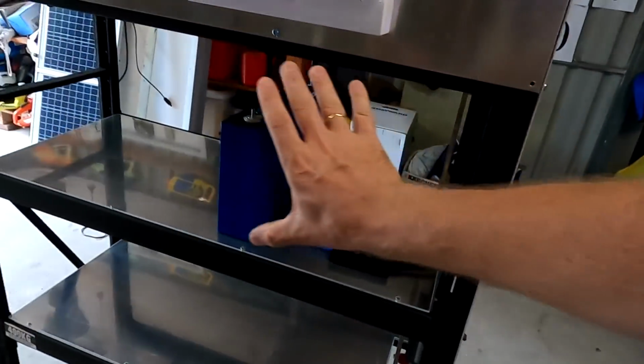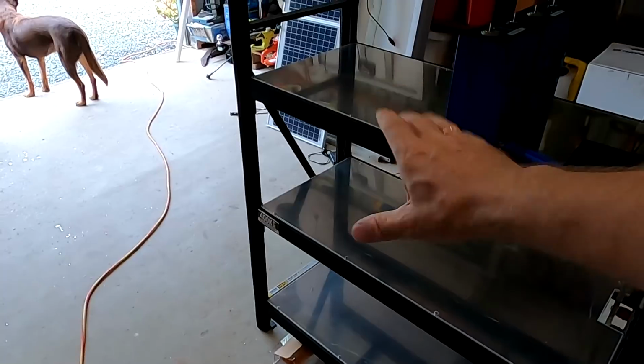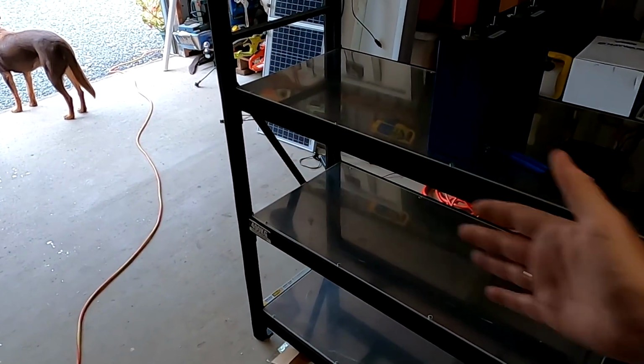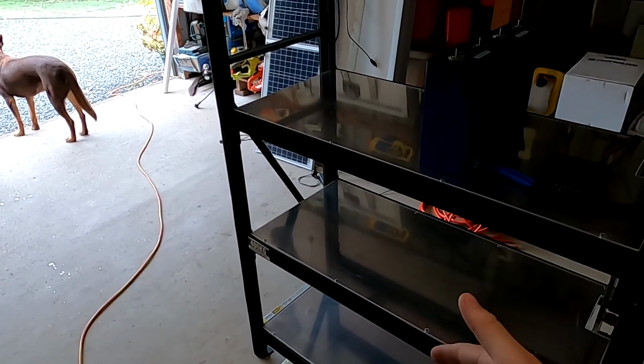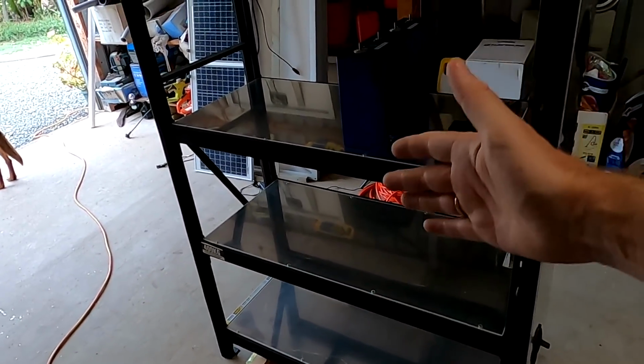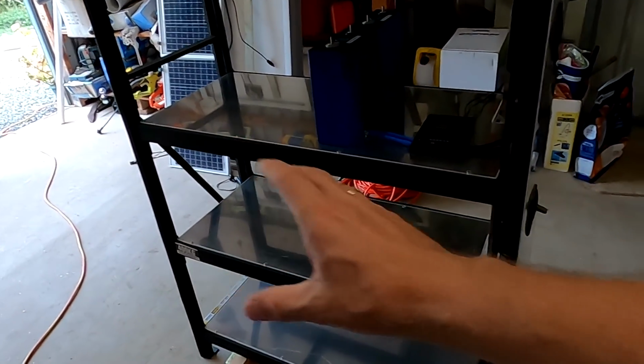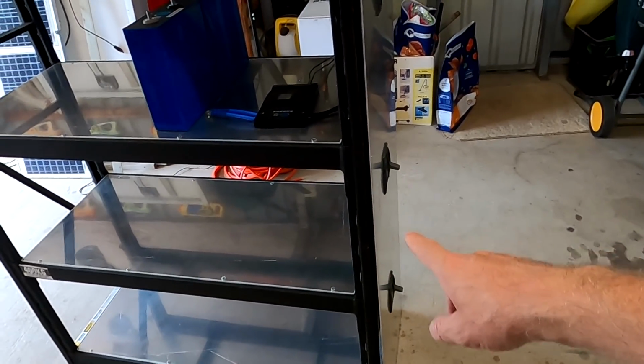There will be separate panels, three of them, so we can take them off individually and just work on one battery side, and the other two batteries are still in operation, getting charged and discharged, and we can isolate one of the batteries here and keep working on it. So this is the whole plan. Sorry, there will be no LEDs, at least not inside the battery cabinet.